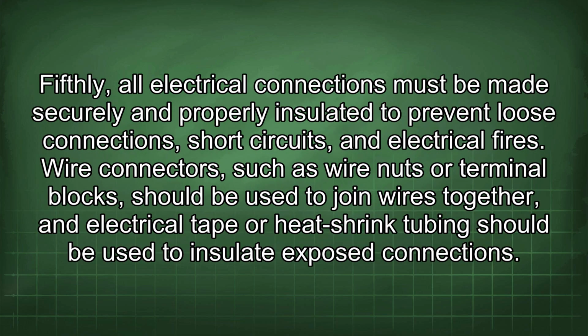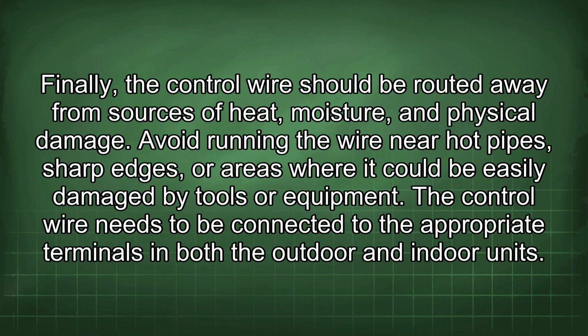Fifthly, all electrical connections must be made securely and properly insulated to prevent loose connections, short circuits, and electrical fires. Wire connectors, such as wire nuts or terminal blocks, should be used to join wires together, and electrical tape or heat shrink tubing should be used to insulate exposed connections. Finally, the control wire should be routed away from sources of heat, moisture, and physical damage.